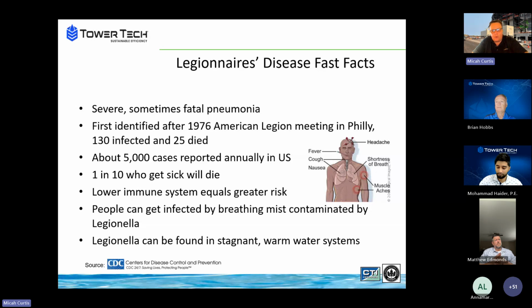I thought it was also an old cooling tower, like originally happened at the 76 American Legion convention. Come to find out, it was a 2-year-old cooling tower. We're not calling out any manufacturer by name. It was basically a brand new cooling tower, and it was not even necessarily not maintained well. So that opened my eyes and I thought, wow, this is something to be taken seriously. And I wanted to mention that to the group. So it doesn't necessarily have to be an old, not maintained cooling tower. It can happen on new equipment very quickly.